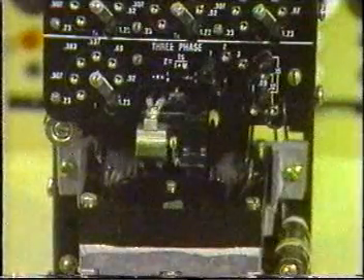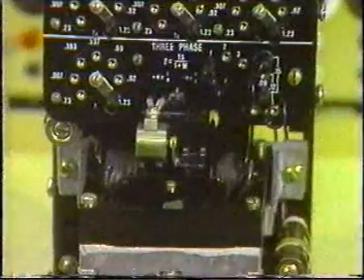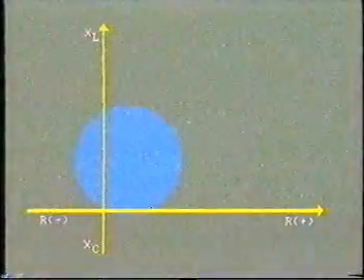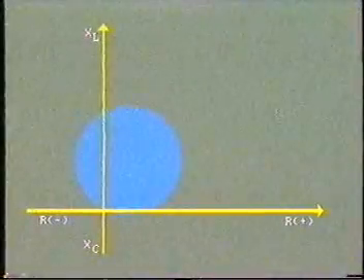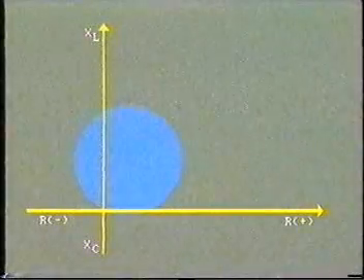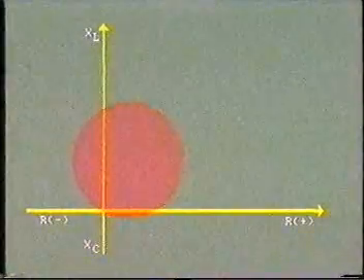Coils are wound around the electromagnet and fed from the CTs and VTs of the primary circuit. The circuitry is designed to give the relay specific characteristics as shown by this circle diagram. The relay will operate if the measured impedance from the point of origin falls within this circle.